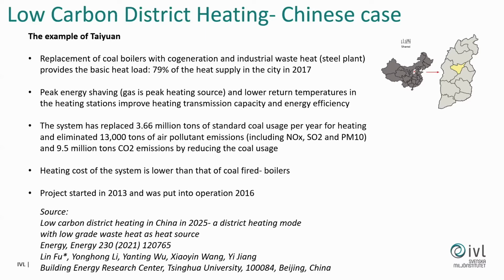For peak energy shaving, gas was used, but by using this method and lowering return temperatures in the heating stations, heating transmission capacity and energy efficiency were improved. In sum, the system replaced 3.66 million tons of standard coal usage per year for heating, eliminating 13,000 tons of air pollutant emissions and 9.5 million tons of CO2. It was also noted that the heating cost of the system was lower than that of coal-fired boilers.